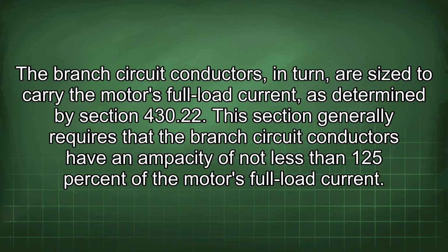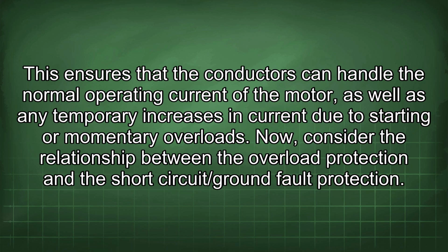The branch circuit conductors, in turn, are sized to carry the motor's full load current, as determined by Section 430.22. This section generally requires that the branch circuit conductors have an ampacity of not less than 125% of the motor's full load current. This ensures that the conductors can handle the normal operating current of the motor, as well as any temporary increases in current due to starting or momentary overloads.